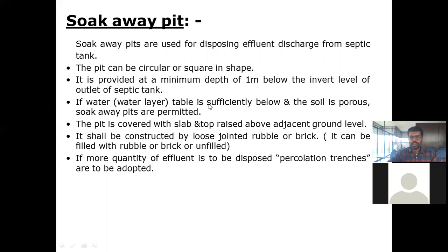If the water table is sufficiently below and the soil is porous, soakaway pits are permitted. When you are trying to provide a soakaway pit in a particular area, the soil should be porous, or it should have the ability to absorb the water, as well as the water table should be sufficiently below, because otherwise it will directly mix with the water. You understood? So the water table should be below the bottom of the soak pit.